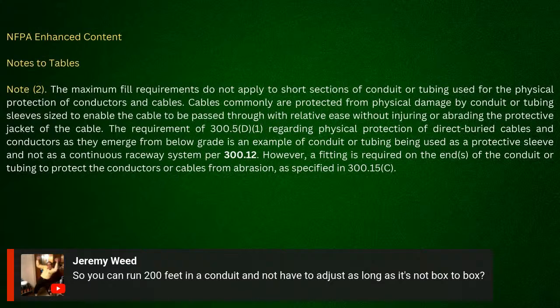Yeah, I was going to say that the large majority of the stuff that we see on gas and oil is less than 10% of the run. So if it's less than 10% of the run, you can use 310.15, less than 10% of the run.